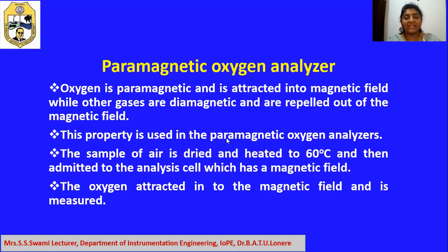The sample of air is dried and heated to 60 degrees centigrade and then admitted to the analysis cell, which has a magnetic field. The oxygen attracted into the magnetic field is going to be measured.